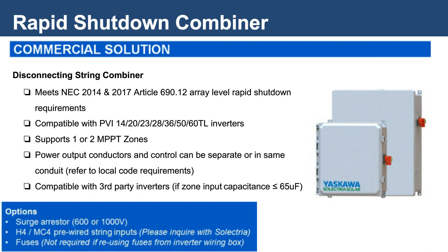This box comes in a variety of flavors. We can support single or dual MPPT zones, depending on the inverter technology, as well as the array layout for your PV system. The boxes utilize a control power signaling to allow you to initiate the rapid shutdown at the same location as your main electrical service and inverter connection points.